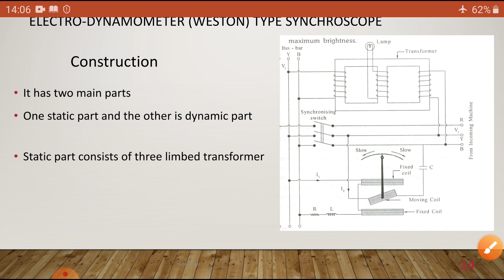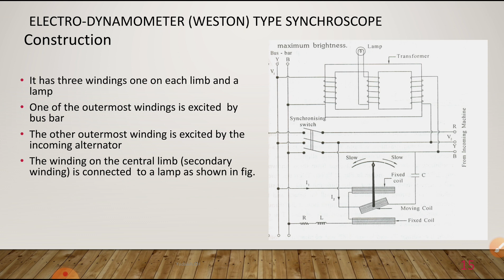Now, it has 3 windings on each limb, and a lamp is connected to the center limb. One of the outermost windings is excited by the existing bus bar, and the other outermost winding is excited by the incoming alternator. You are observing here, this is connected to V1, this is connected to V2 - incoming is the new one, existing is the local one.